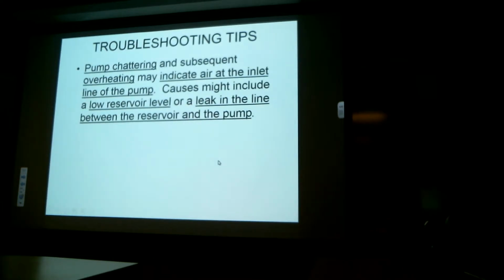Pump chattering, subsequent overheating might indicate that air is at the inlet of the pump. Causes might include a low reservoir level, a leak in the line between the reservoir and the pump. The chattering, I guess, is really a more severe condition of cavitation in the pump, but nevertheless, it'll sometimes cause it to chatter.